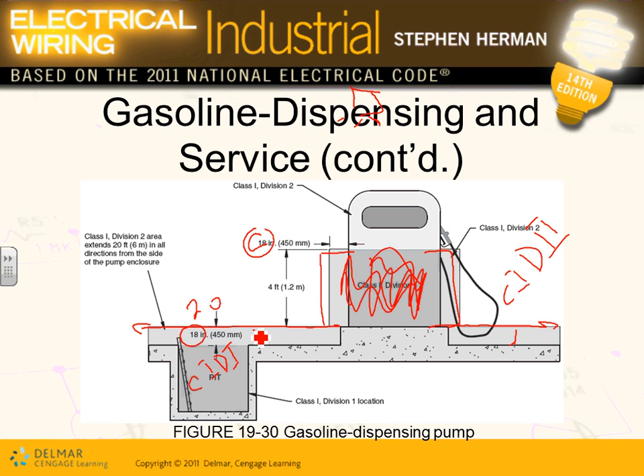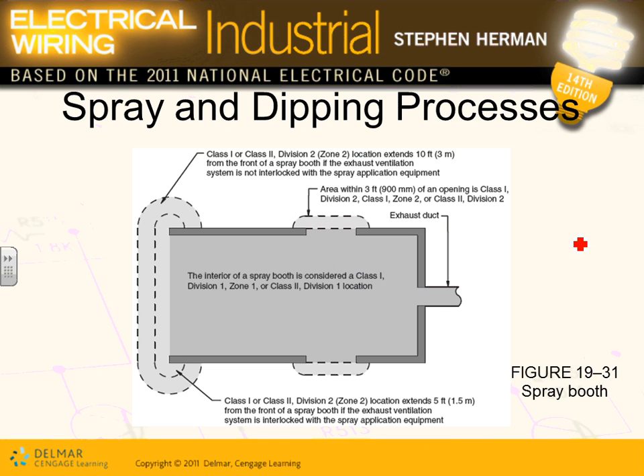In a gas station like this, they also require you to have an emergency push button. If you walk into a gas station and there's a spill, that button should be not closer than 20 feet and not further than 100 feet. You run to that button, push it, and shut down the pump, or all the pumps in that area. So you stop the spill before it ignites. Any comments, guys, about these hazardous locations? Now, anything you put in a class 1 div 1 is going to be explosion proof.